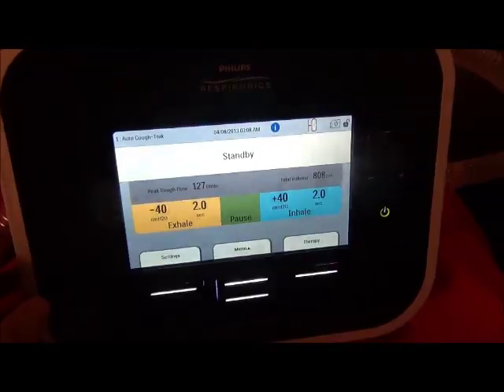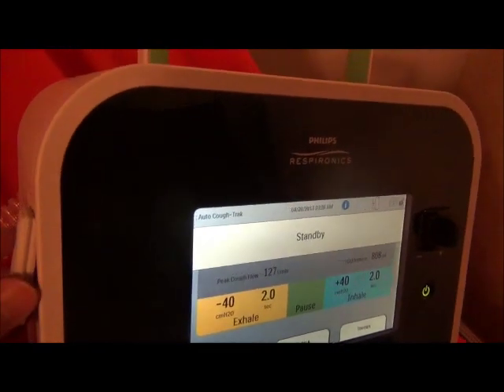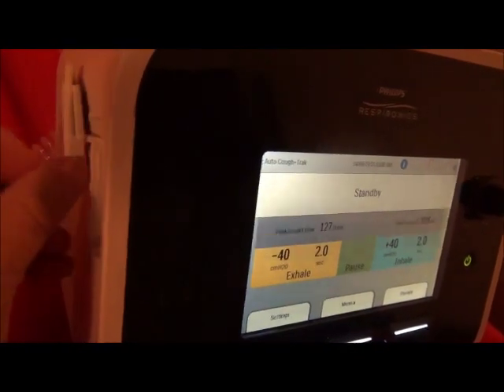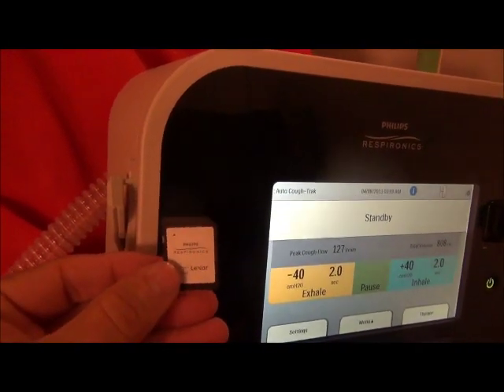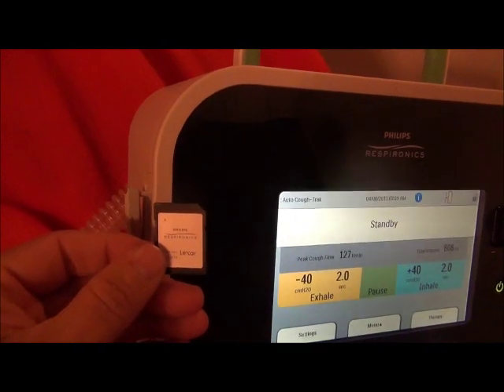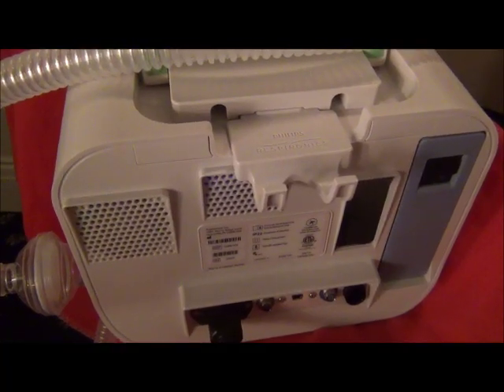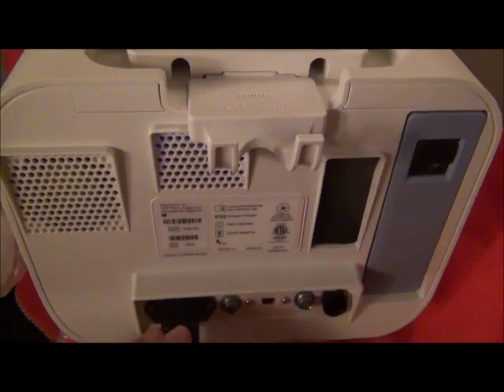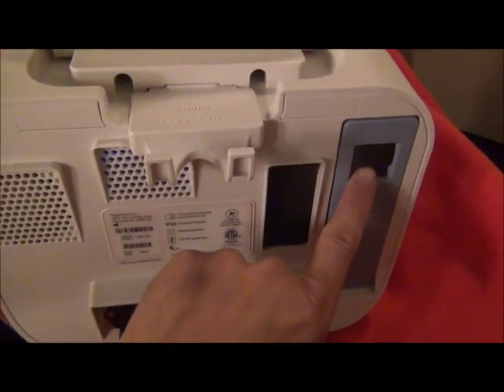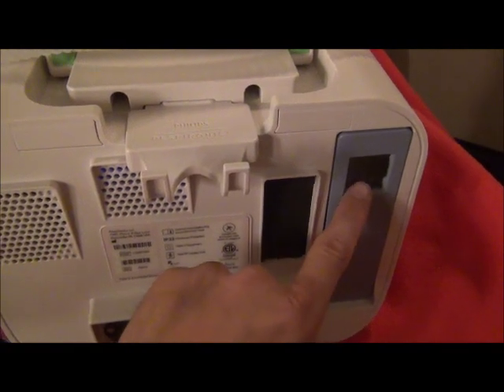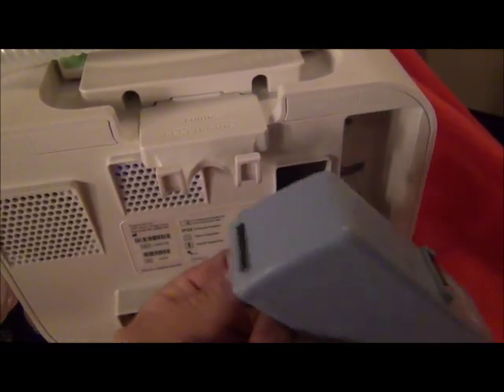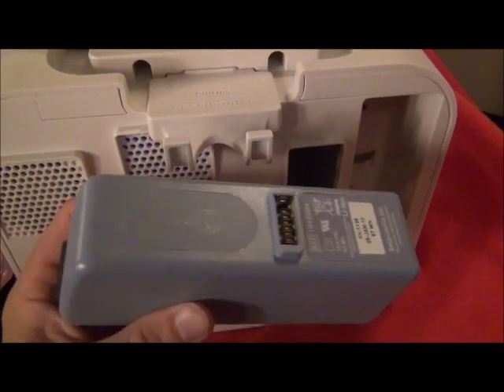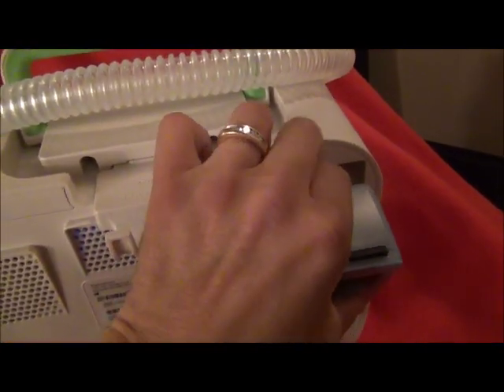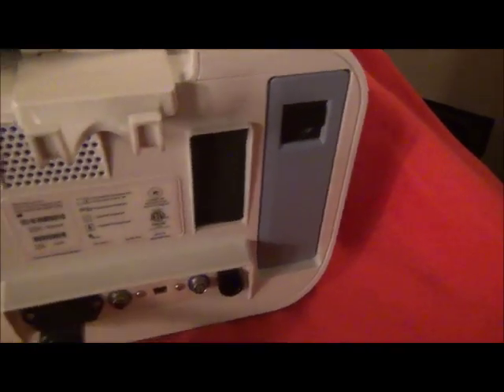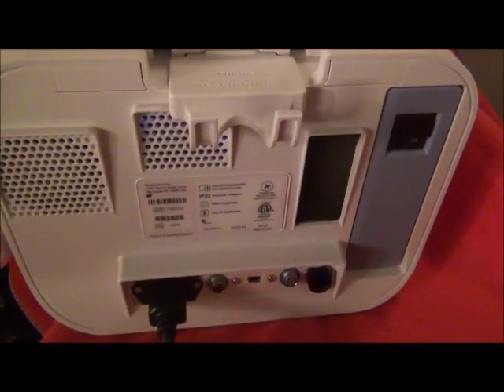The data card is located on the left-hand side. It's got a little rubber cover. I'm going to pull that off, and I can reach in and get the SD card. And I can put that in my computer and use the DirectView software and generate some reports for the doctor. On the back of the T70, I have my filter, the plug input, and also an optional battery. Now this doesn't come with a battery standard. I actually took a Trilogy ventilator battery and plugged it in. I had to take the cover off. It took a little while to get it off. And so I can actually run this 3 hours with a battery backup.